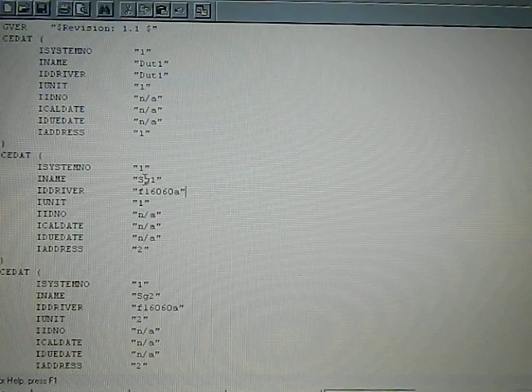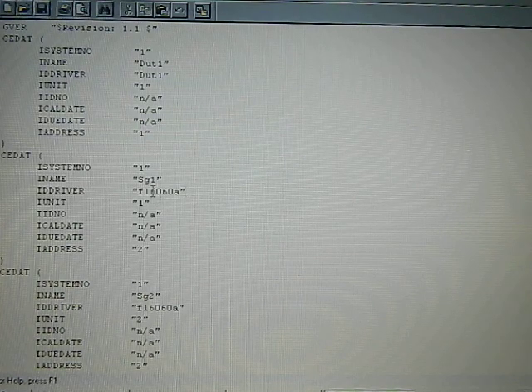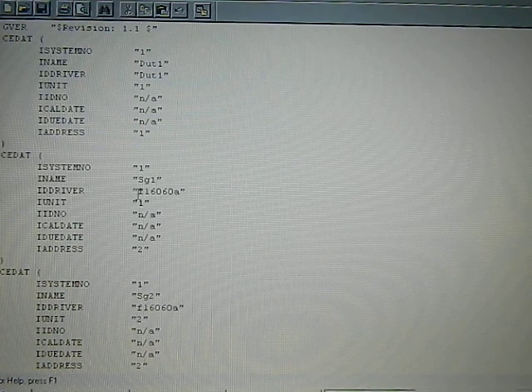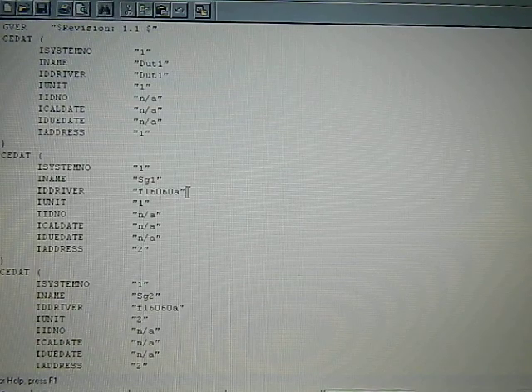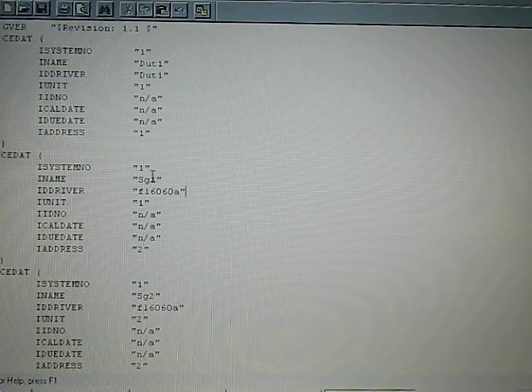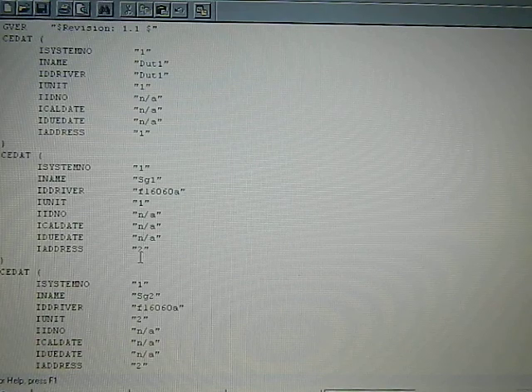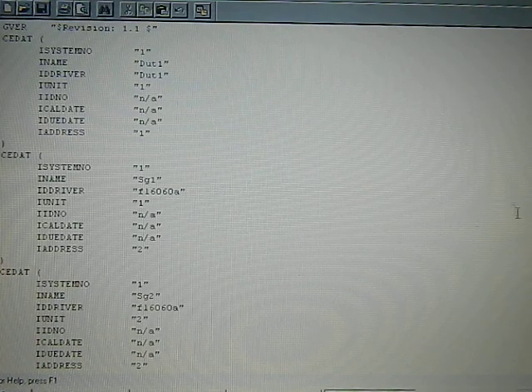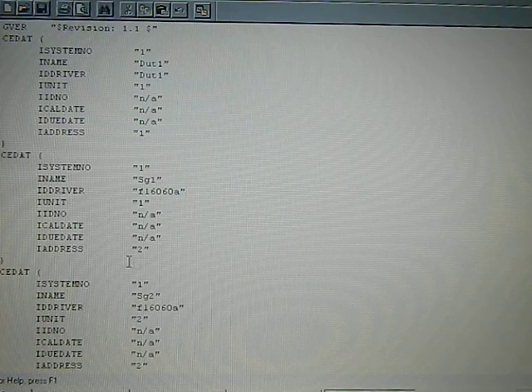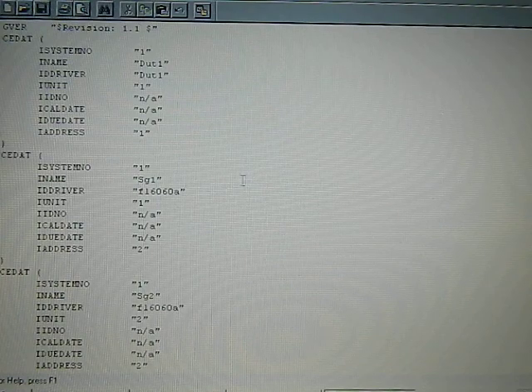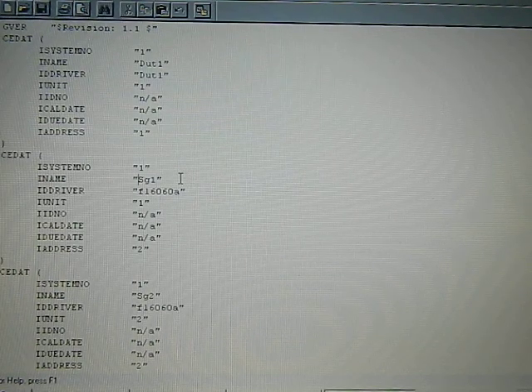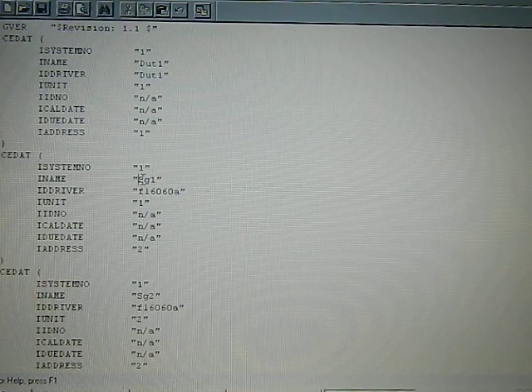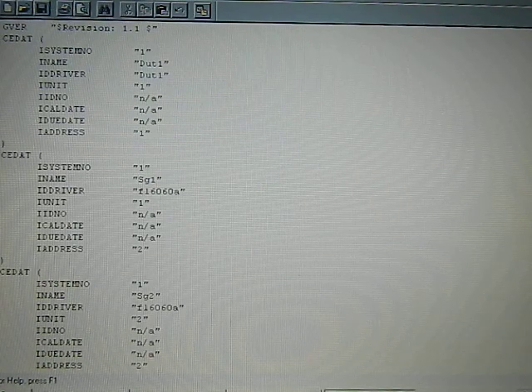You can see that for the signal generator 1, I've assigned it Fluke 6060A, which is a valid instrument as far as the software is concerned. And it's signal generator 1, and its address is number 2. And I think that's the way the factory had it originally, number 2. They put a little star here in front of it to tell the software to ignore, not to look for this instrument, so you need to take that away.